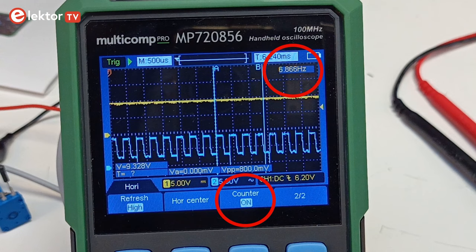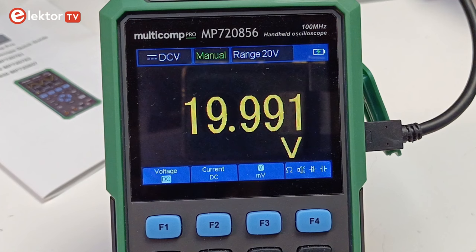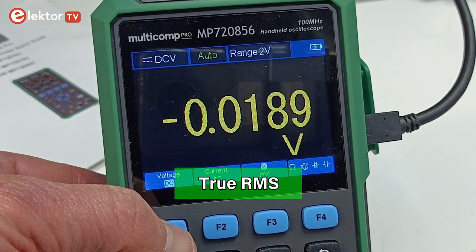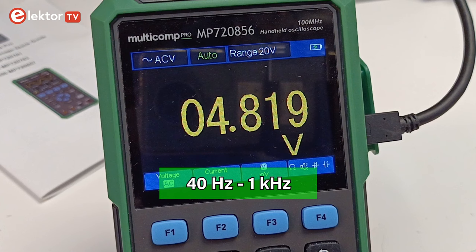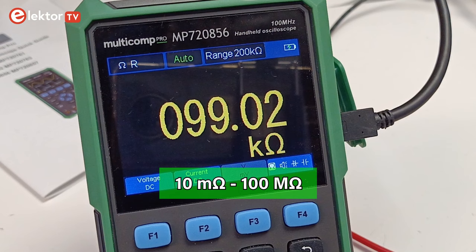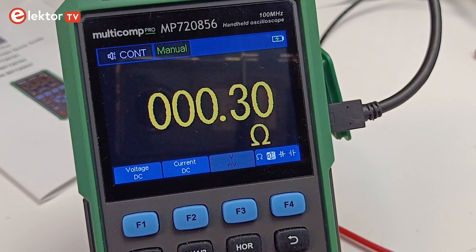The Multicomp Pro MP720856 is also a 20,000-count multimeter with a DC range from 200 mV up to 1000 V, and a true RMS AC range from 200 mV up to 750 V for frequencies from 40 Hz up to 1 kHz. AC and DC currents up to 10 A are supported. The ohmmeter range is from 10 mΩ up to 100 MΩ, and the capacitance range is from 1 pF to 2 mF. Diode and continuity testing is possible too.